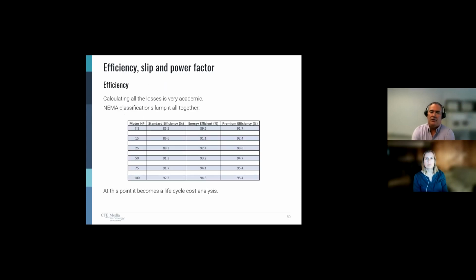It's very academic and difficult to try and calculate all of that, okay? Especially the current losses and the iron losses, because those are all a function of speed and horsepower and load, et cetera, et cetera. So NEMA jumps in and says, well, I'm going to give you some classifications. I'm going to give you standard, energy efficient, and premium. And if your motor wants my NEMA stamp of approval to fall into one of these categories, this is how it must perform. And you'll see that the higher the horsepower of the motor, the more efficient we want it to be. And again, now it becomes a life cycle cost analysis or an economics discussion. Because if I need 15 horsepower, whether I do it in standard, energy efficient, or premium, from the work perspective, I don't care. I'm still getting 15 horsepower. What I care about is how much it is going to cost me to get that 15 horsepower.